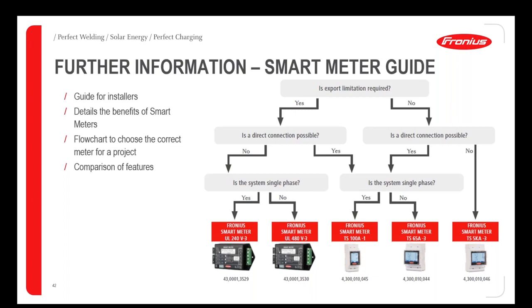Open it up and have a look at the flowchart. When you're installing a new system, it's worth working through this flowchart to determine which smart meter to use. So, for example, if you want a site with export limitation and a direct connection is possible, and it's a single phase system, you'll be guided through to the Fronius TS100 meter.